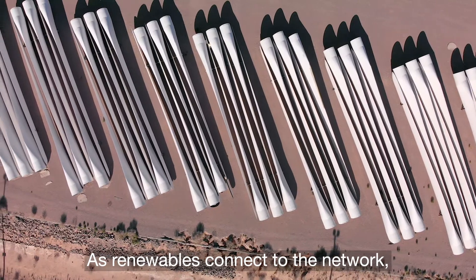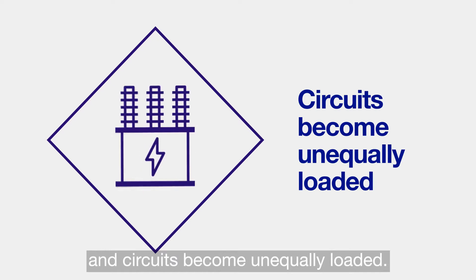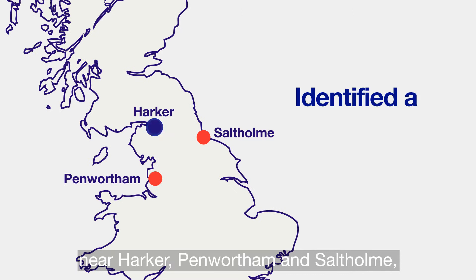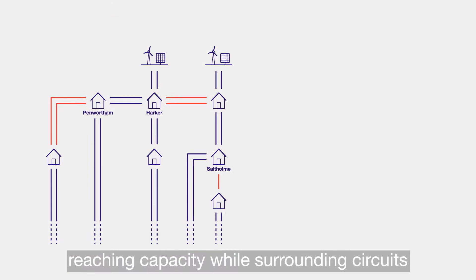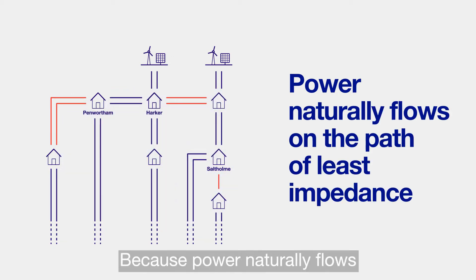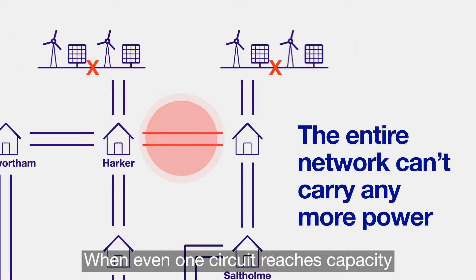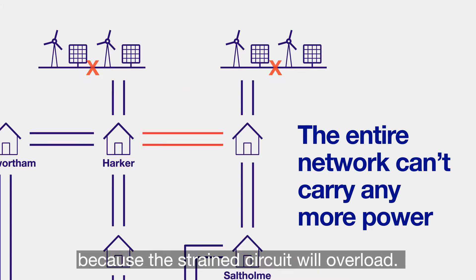As renewables connect to the network, power flows change and circuits become unequally loaded. Circuits in the north of England, near Harker, Penwortham and Saltholme, were identified as bottlenecks of renewable power flows, reaching capacity while surrounding circuits were still below their limits. Why? Because power naturally flows on the path of least impedance. When even one circuit reaches capacity, the entire network can't carry any more power because the strained circuit will overload.